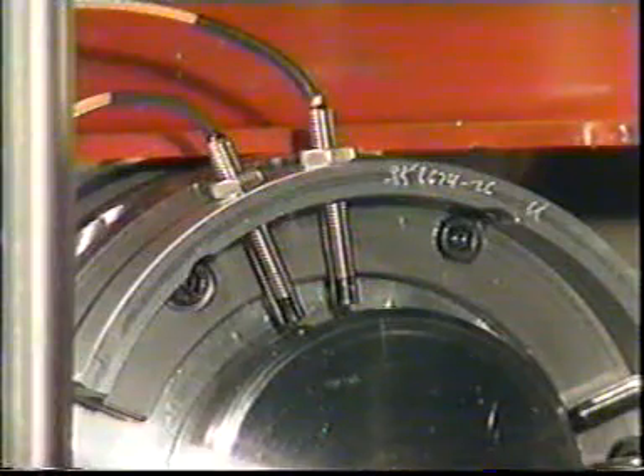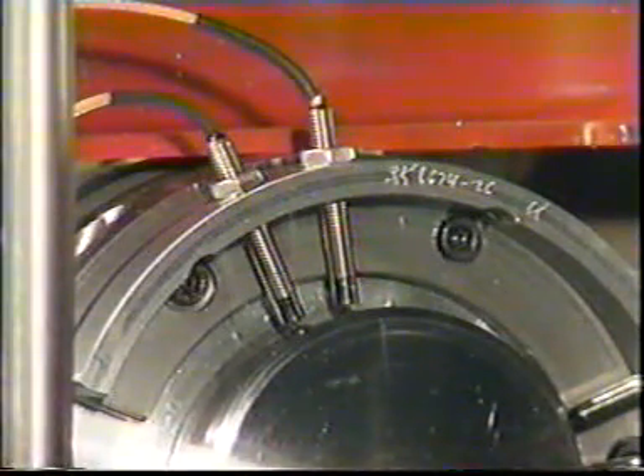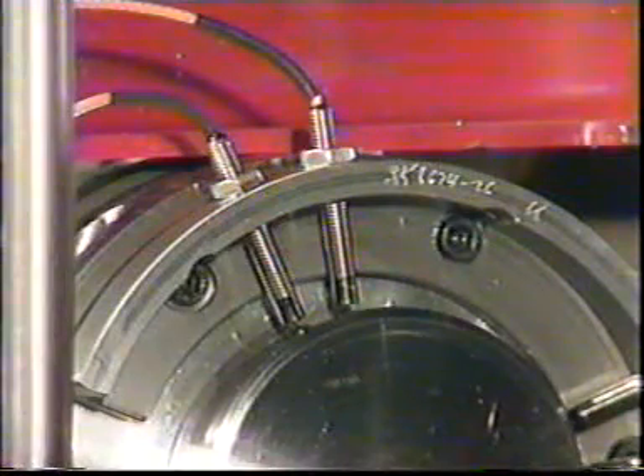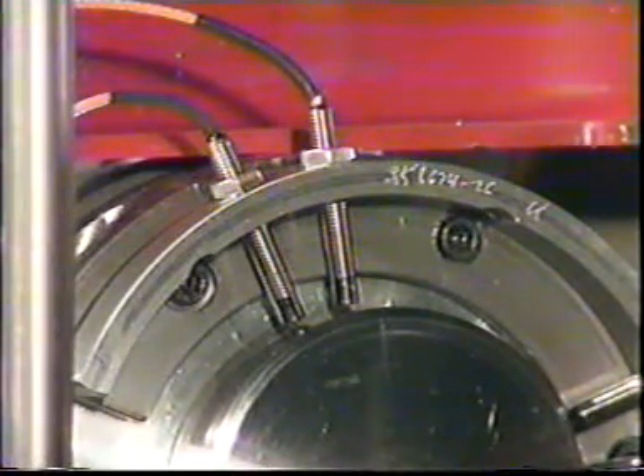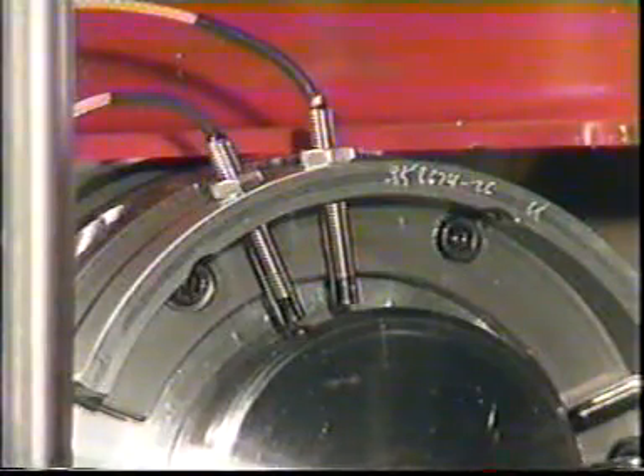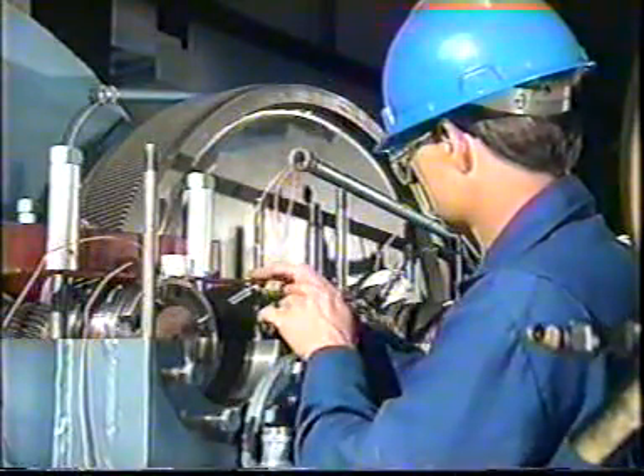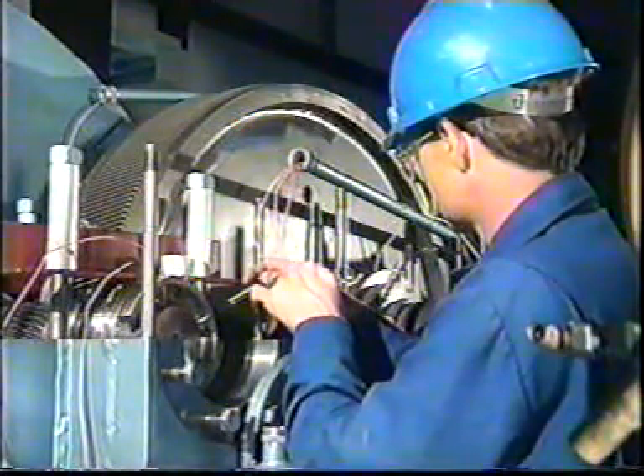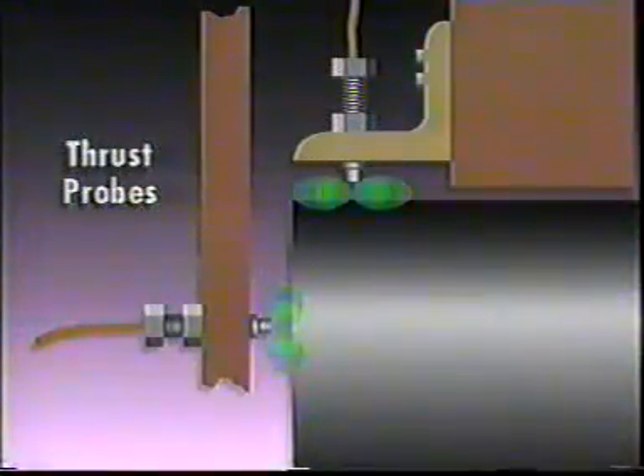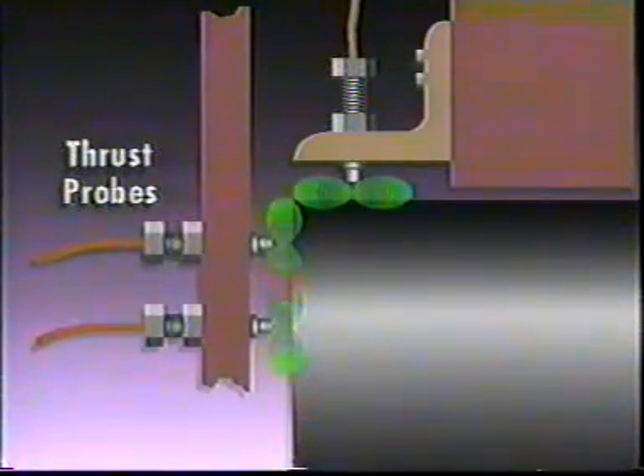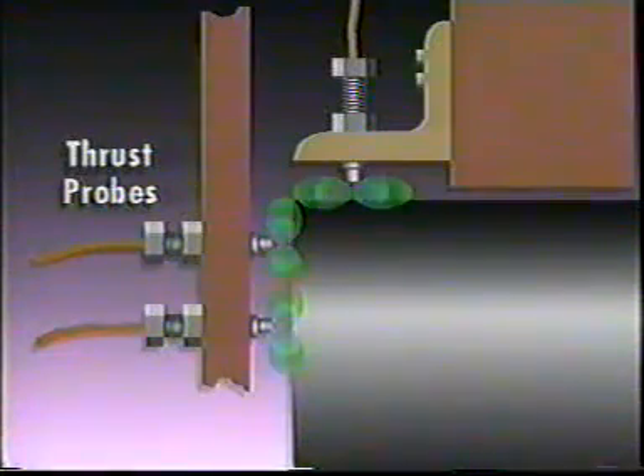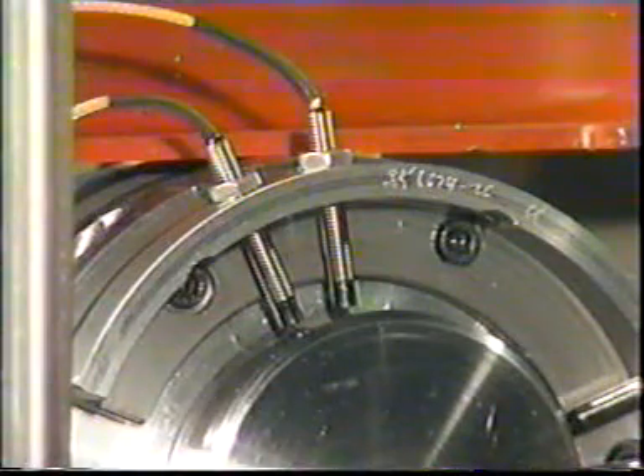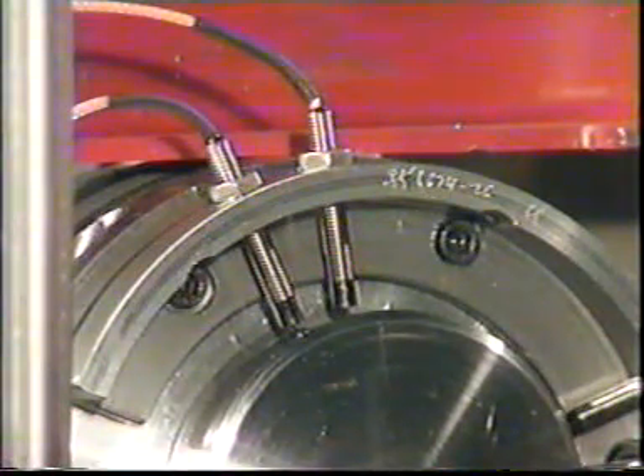Critical machines may have redundant sensors installed so that a single fault or failure will not cause an unnecessary shutdown or allow a machine to continue operating with excessive vibration. Sensors must be carefully positioned, especially redundant proximity probes. Remember, a proximity probe uses an eddy current to create a magnetic field to measure shaft displacement. If 2 probes are too close together, the electromagnetic fields will interact and give each sensor erroneous readings. Proximity probes need to be spaced far enough apart so the fields cannot overlap.